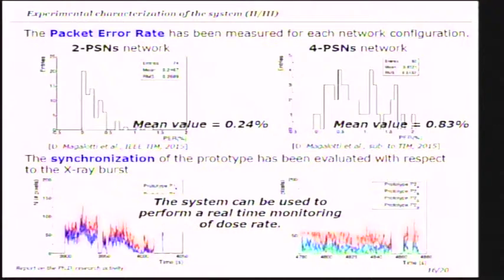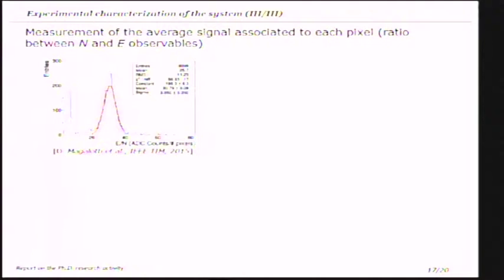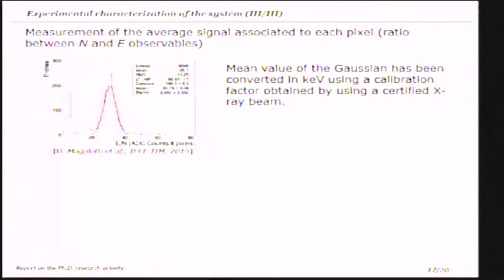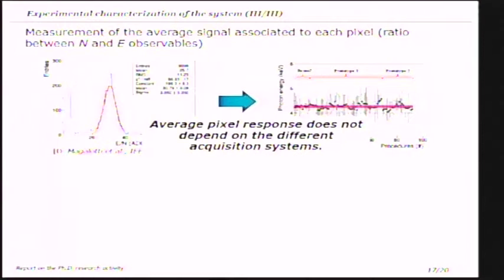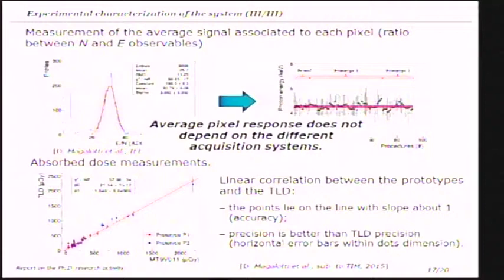The system can be used to perform real-time monitoring of the absorbed dose. I studied the average signal associated to each pixel above threshold by considering the ratio between the two observables — energy and number of pixels. By considering the mean value of the distribution, we convert it to photon energy. As a function of different interventional radiology procedures, the mean value associated to each pixel above threshold is constant and does not depend on the acquisition system, so the sensor performances are not affected by the acquisition system.